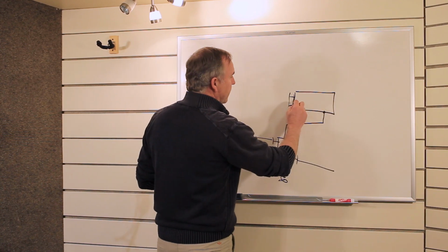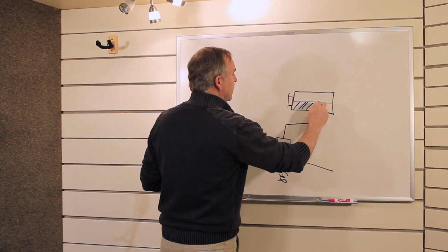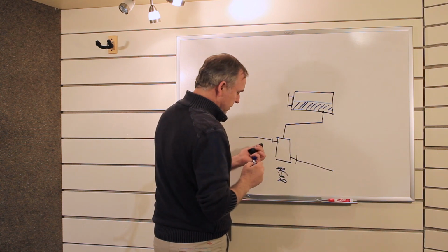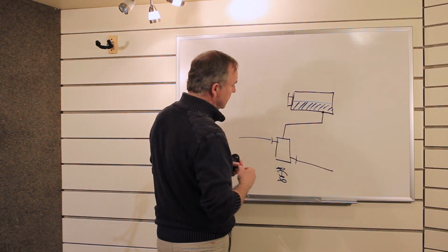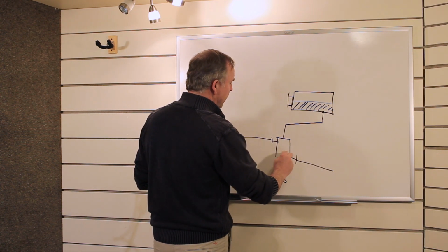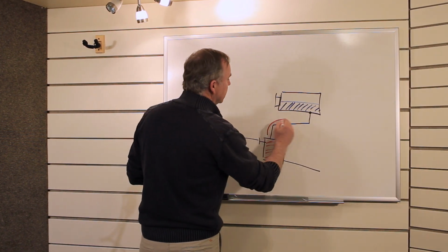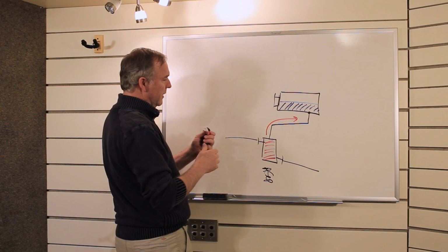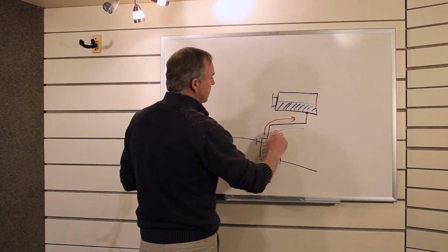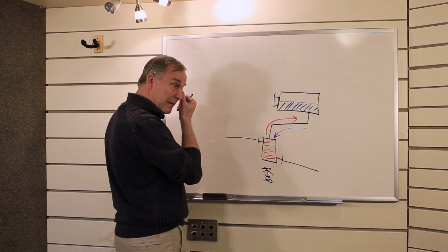It turns out that the water in the tank ends up being cool, and in the heating system, the water down here is going to be hot. That ends up setting up a circulation where the hot water wants to sort of go climbing up that line, and cool water wants to spill down.